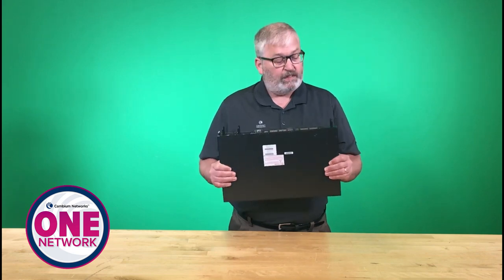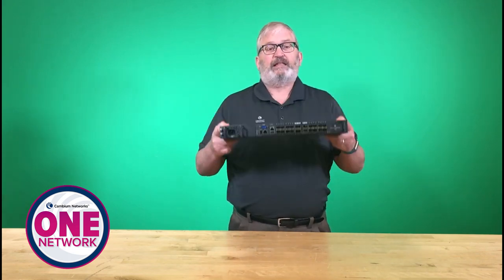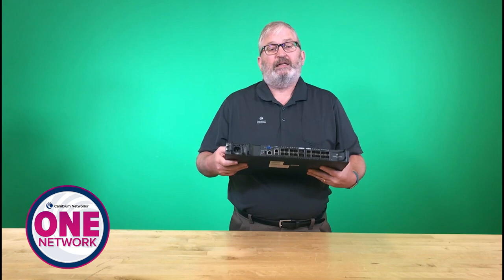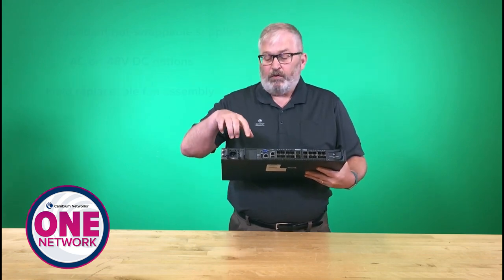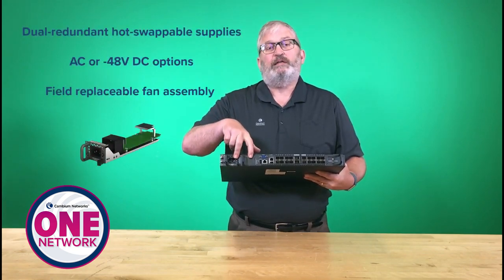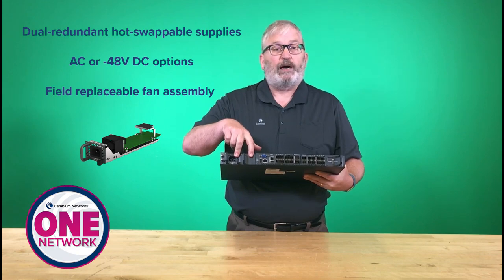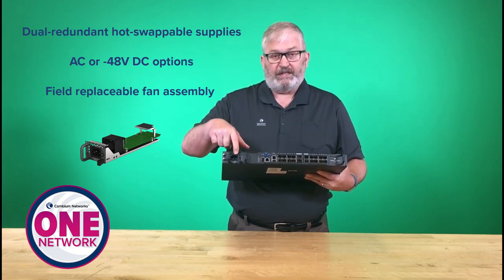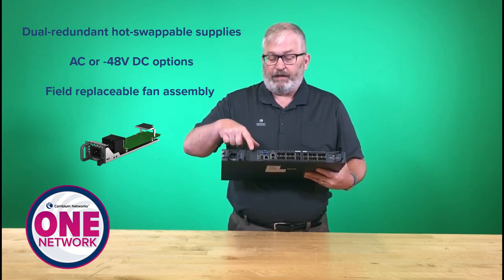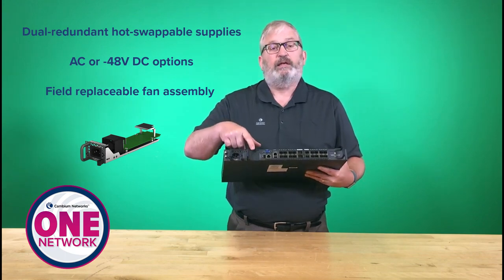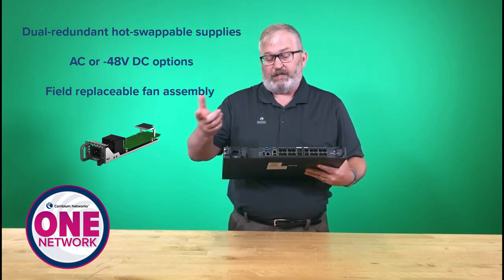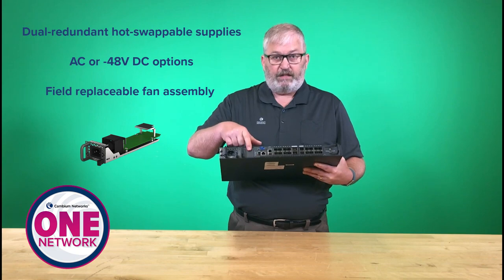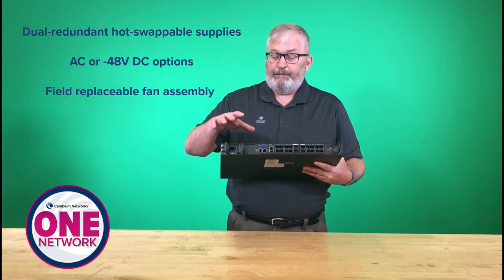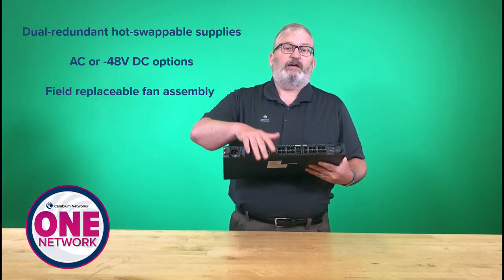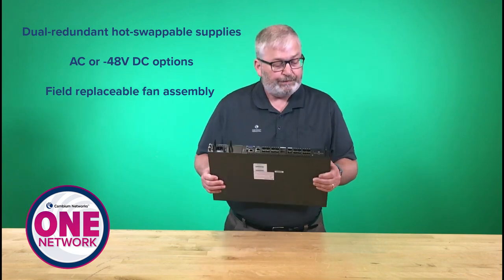Other than that, it's quite a simple box. You can rack mount it, and you can stack these. For resilience and reliability, we have 2 dual redundant hot swappable power supplies. What I'm showing here is an AC power supply, and then there's a bay here where you can put in a secondary supply. So for example, you can put in an AC supply and a DC, a negative 48 volt supply. The AC will take priority and it can fail over to the DC input.